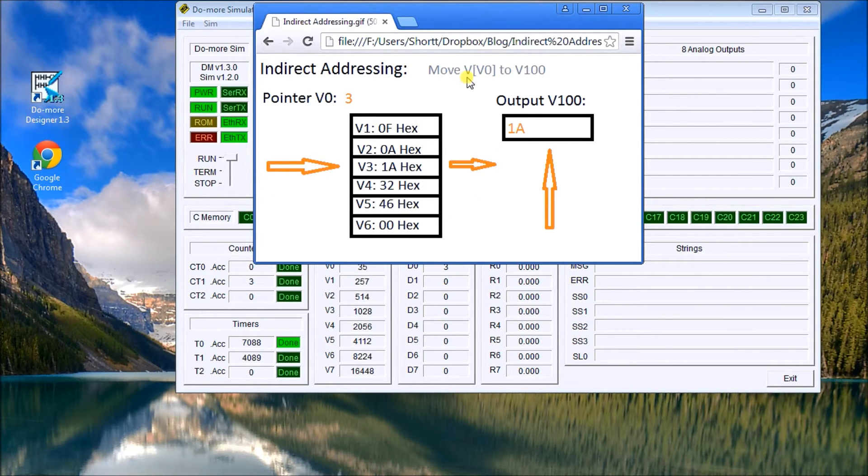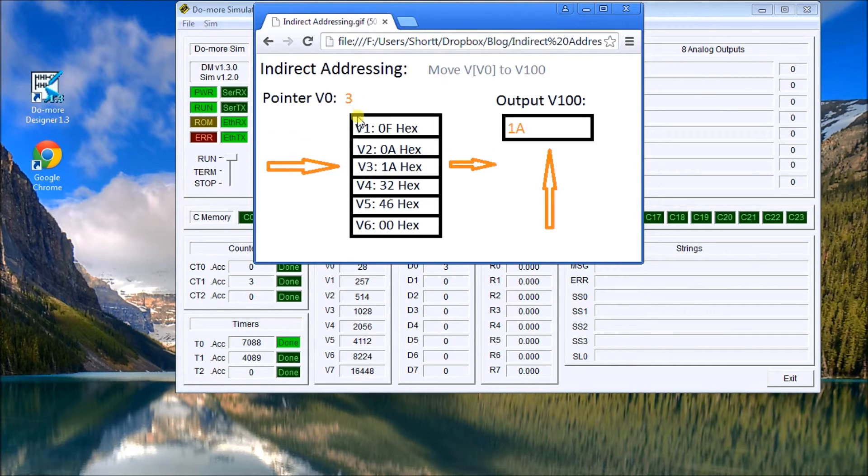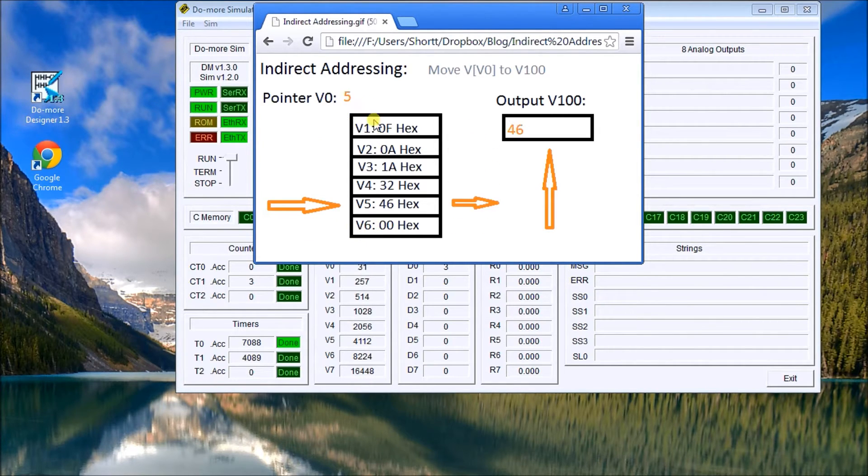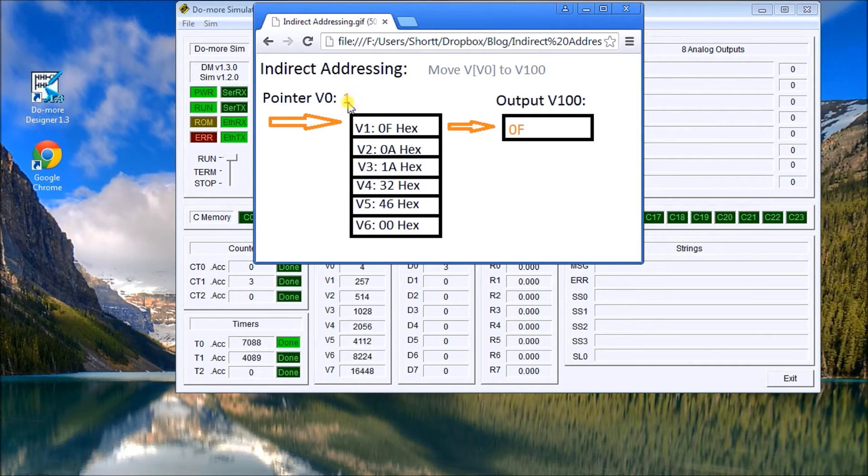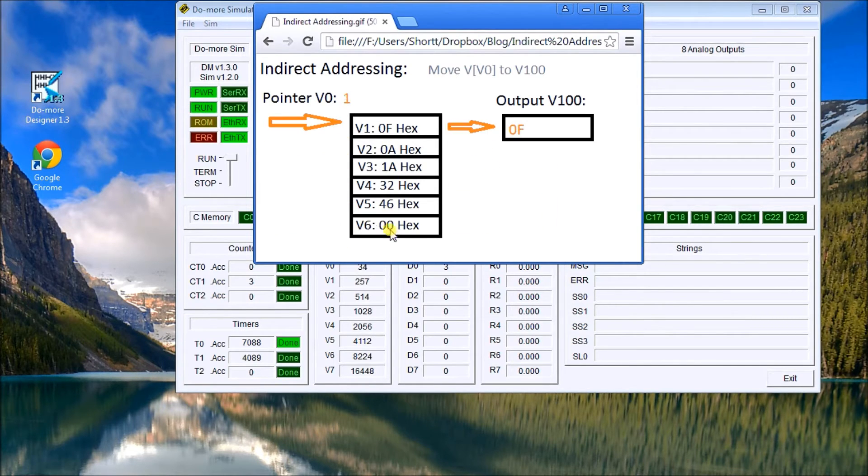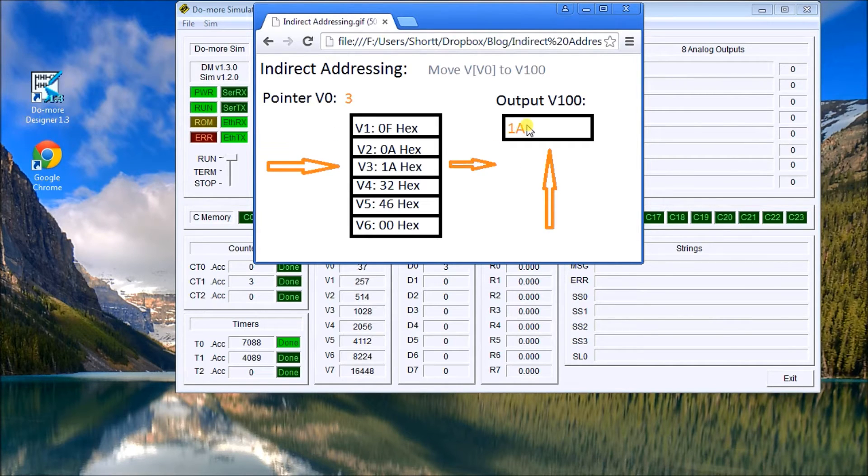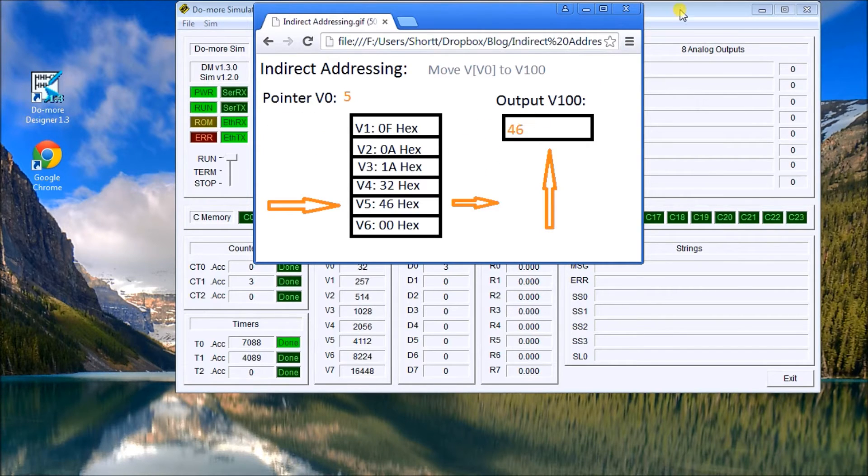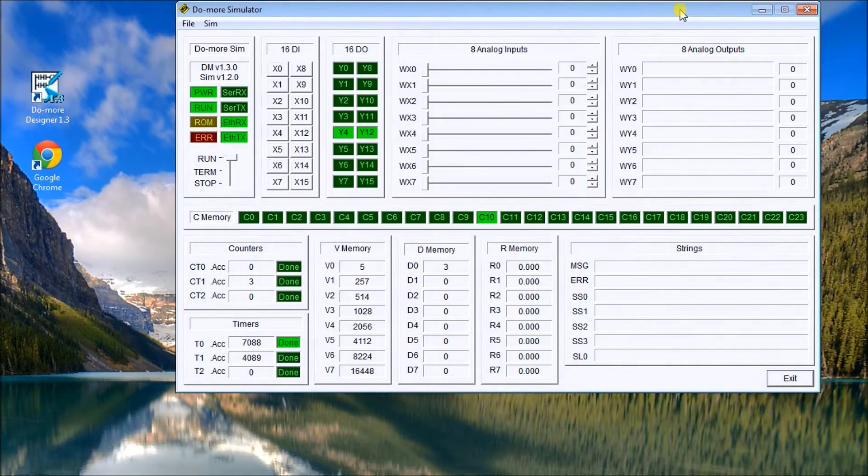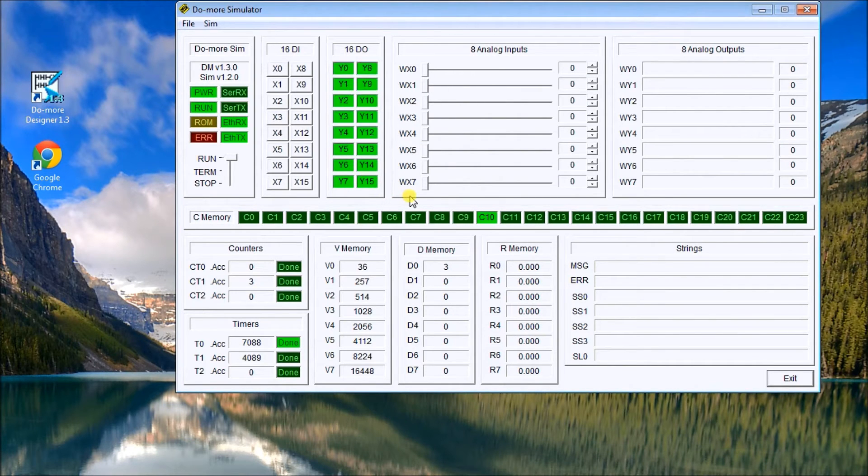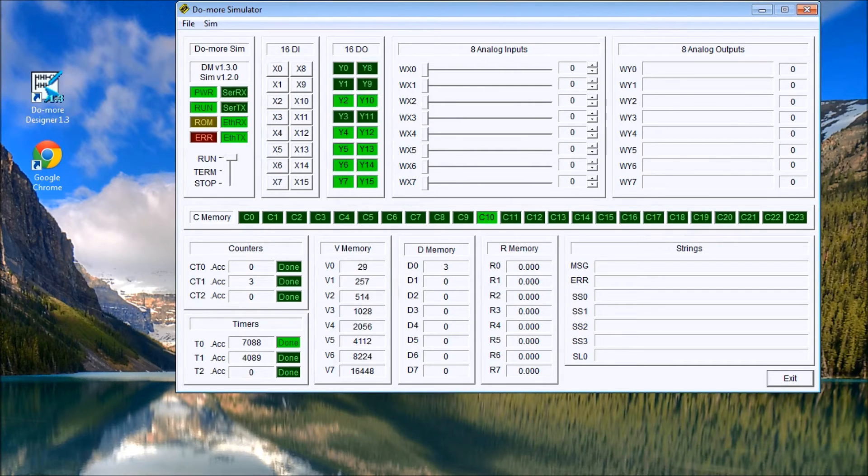V0 is pointing to the location of the V memory locations. So as this moves from 1 to 6, it moves the corresponding output to the actual output channel. So that basically is how indirect addressing really works. Looking back at our lights, you see here again it's just a sequence. So let's call up the actual program.